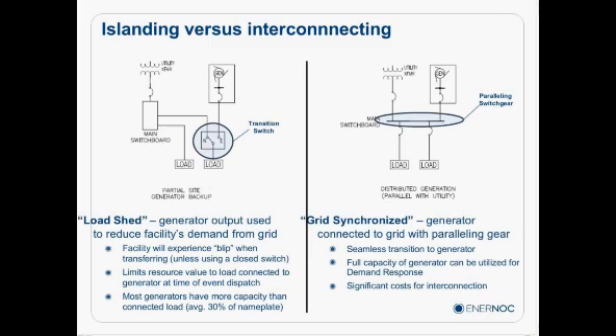Islanding versus interconnecting. Most customers island, meaning they have an open transition transfer switch where they take their load and completely disconnect from the grid. This is an easier, less expensive installation, and since most customers already have open transition transfer switches, it makes for faster deployment. The challenge is that the customer will see a blip when transitioning from utility power to on-site power, and you're limited to the load connected to the generator. Most generators run at a relatively low percentage of their capacity.